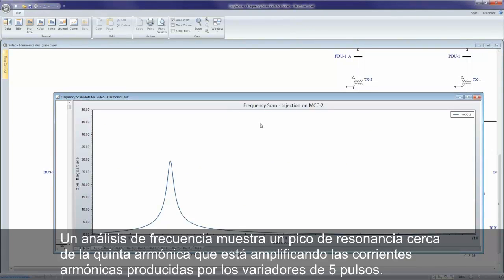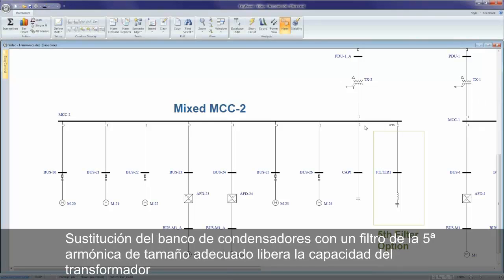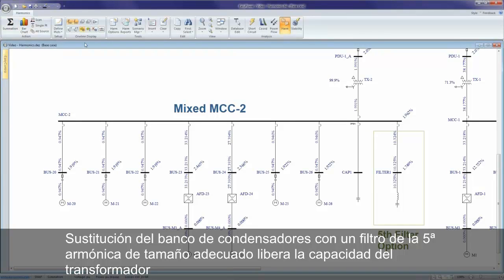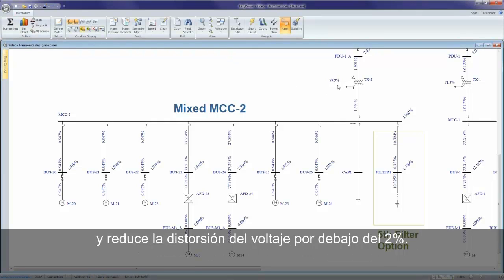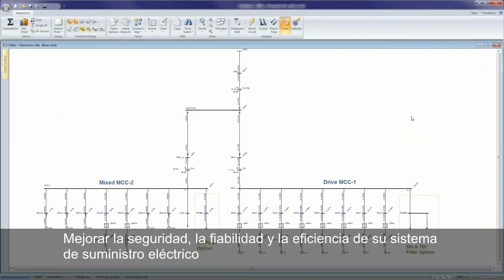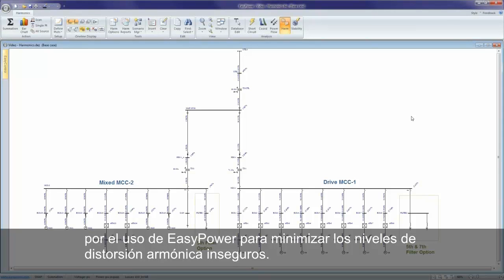A frequency scan shows the resonant peak near the fifth harmonic, which is amplifying the harmonic currents being produced by 6-pulse drives on the bus. Replacing the capacitor bank with an adequately sized fifth harmonic filter releases all the capacity in the transformer and reduces the bus voltage distortion below 2%. Improve the safety, reliability, and efficiency of your electrical supply system by using EasyPower to minimize unsafe harmonic distortion levels.